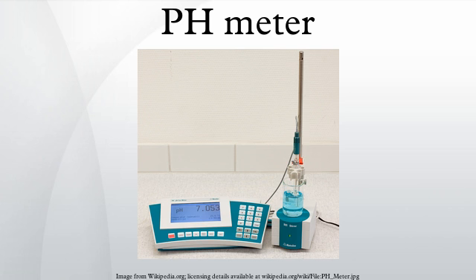Types of pH meters. pH meters range from simple and inexpensive pen-like devices to complex and expensive laboratory instruments with computer interfaces and several inputs for indicator and temperature measurements to be entered to adjust for the slight variation in pH caused by temperature. Specialty meters and probes are available for use in special applications, harsh environments, etc. There are also holographic pH sensors, which allow the measurement of pH colorimetrically.